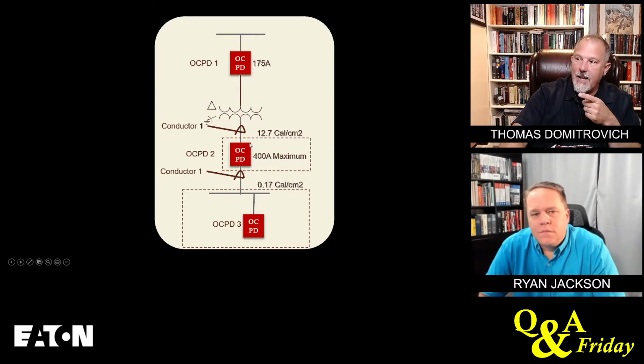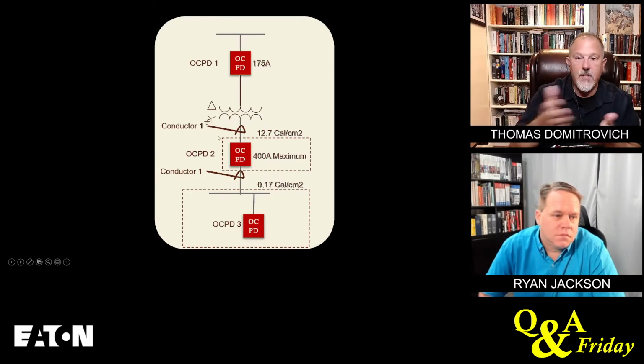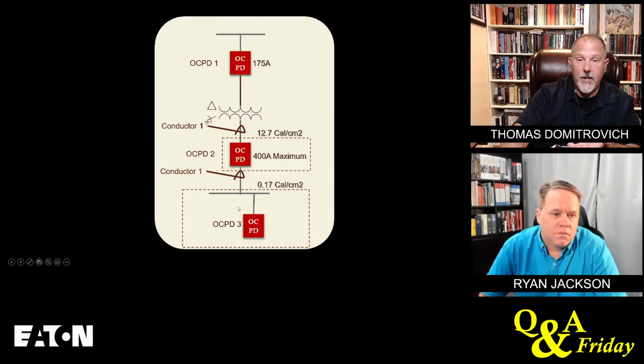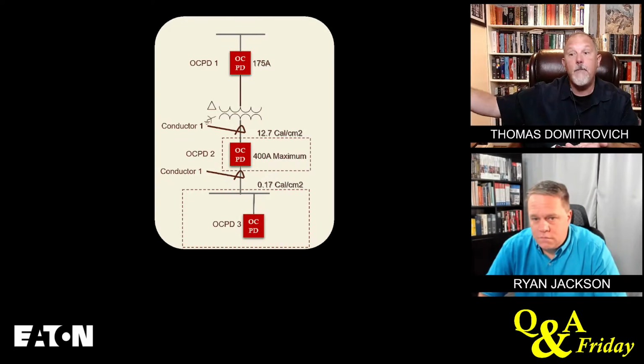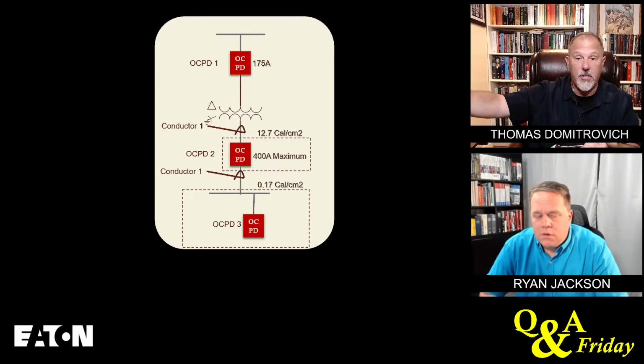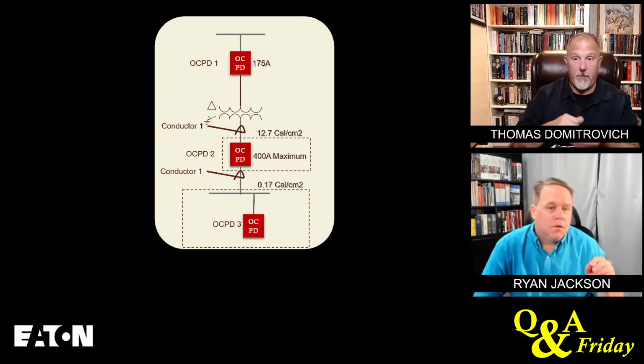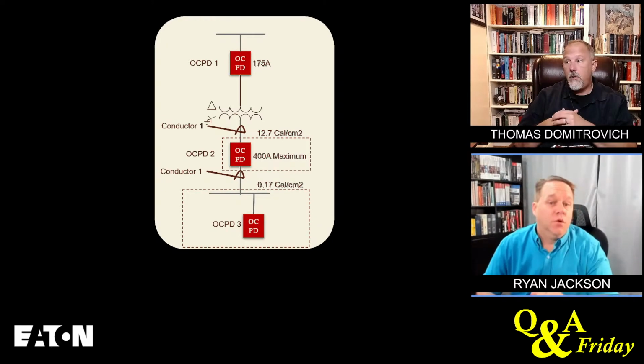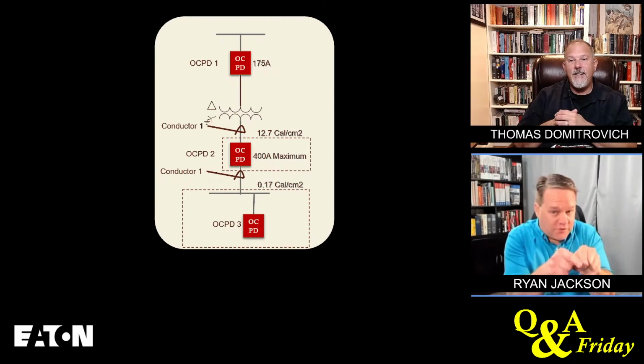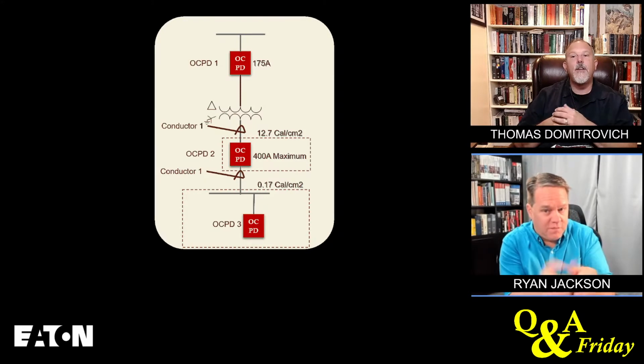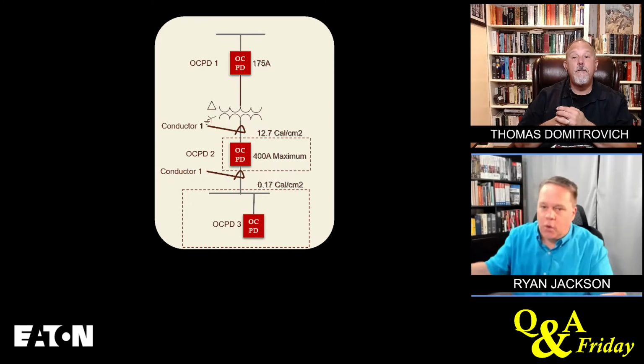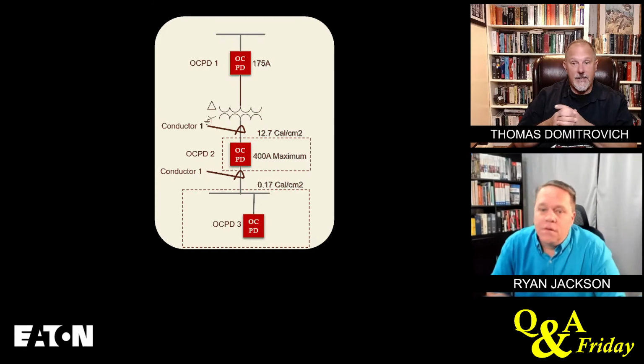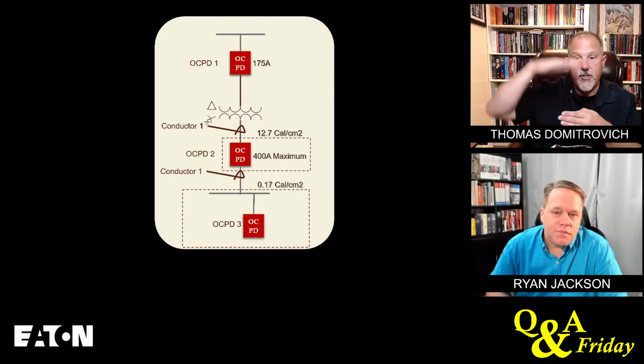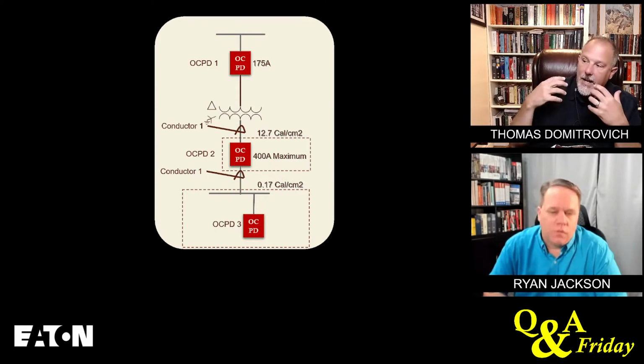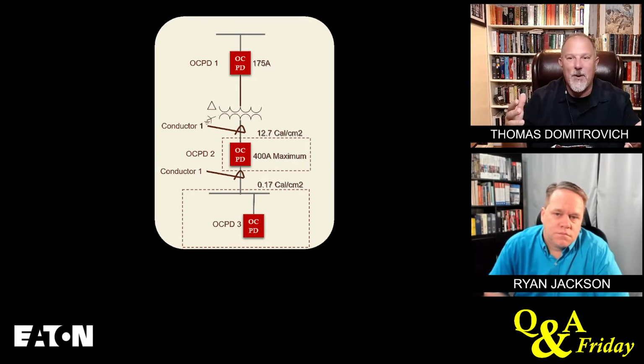That's when we said, well, what if we just incorporated this into the transformer? Your 12.7 calories stays at the transformer, and the incident energy down at that panel where you might be doing justified energized work is only 0.17, which is a huge decrease in incident energy, and that's conservatively high, probably. But when you say the 12.7 moves up, you're saying right at the transformer secondary terminals, it might be 12.7. Yes. But anywhere downstream, it's lower, perhaps less than 1. Yes, exactly. And it depends on the length of the conductors because you're reducing the fault currents. But it was one of those things where I backed into it.